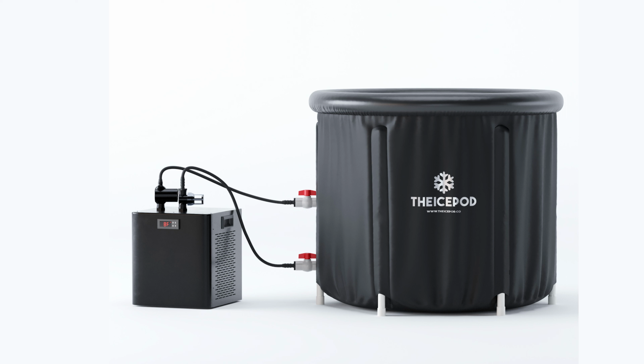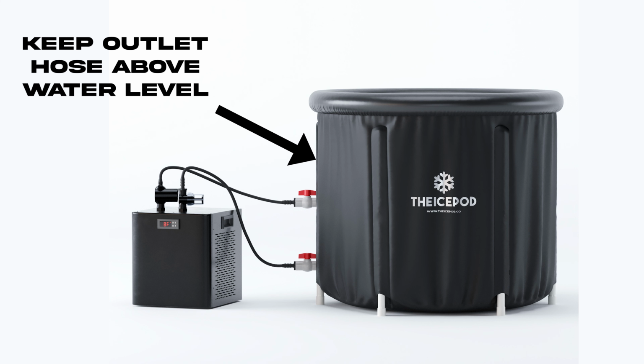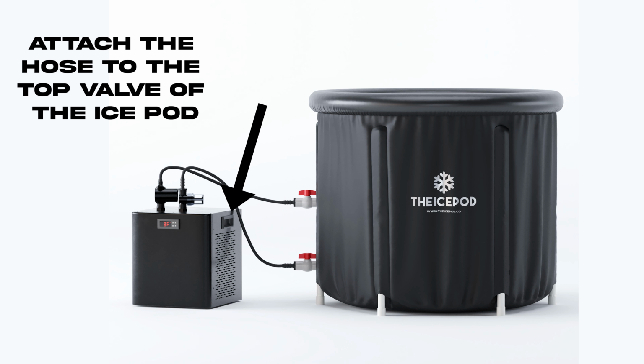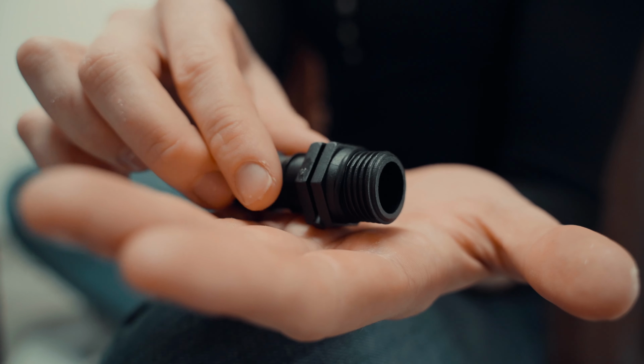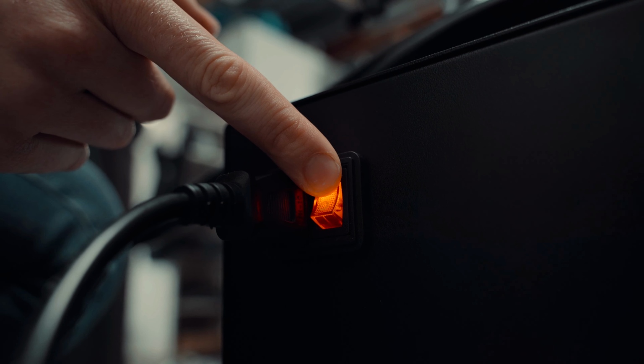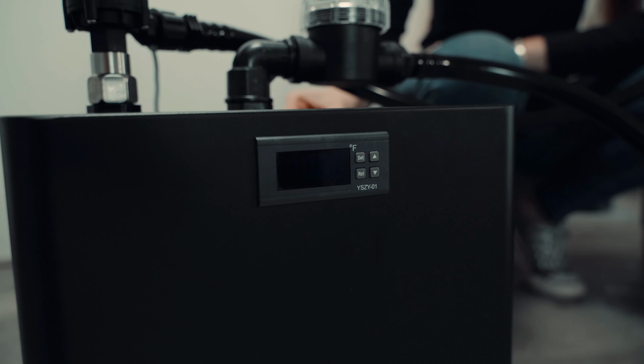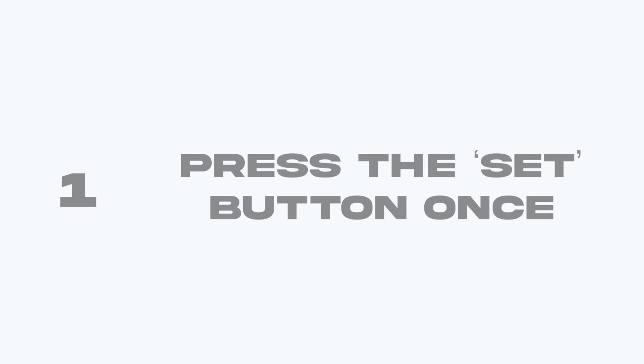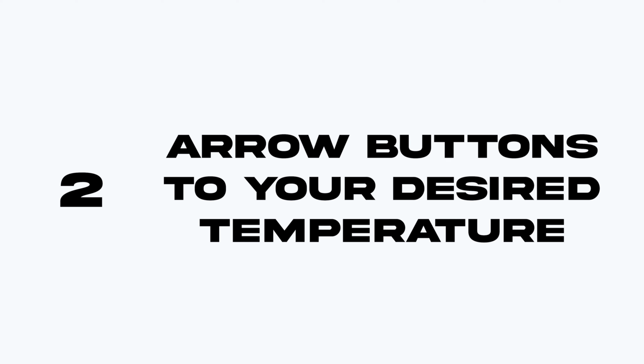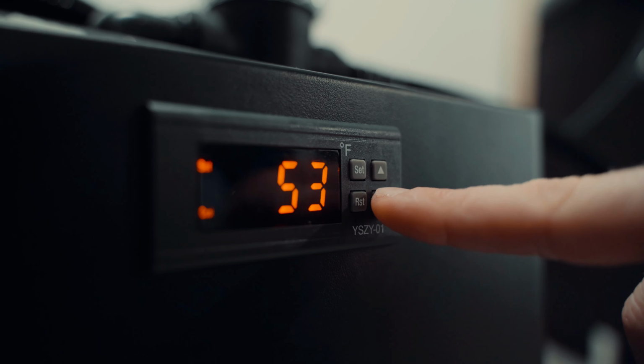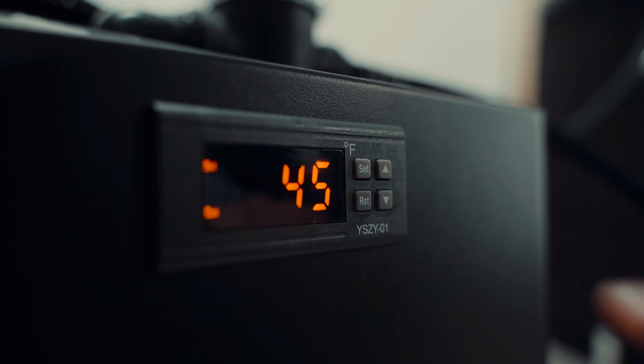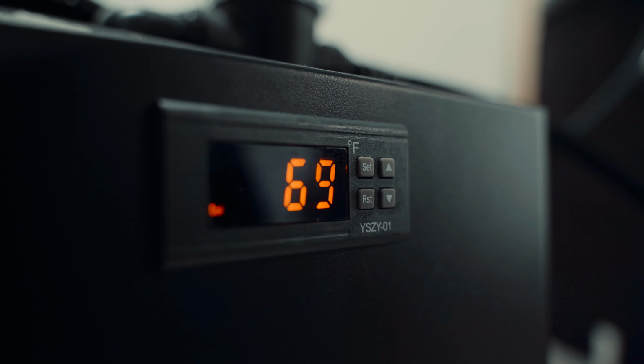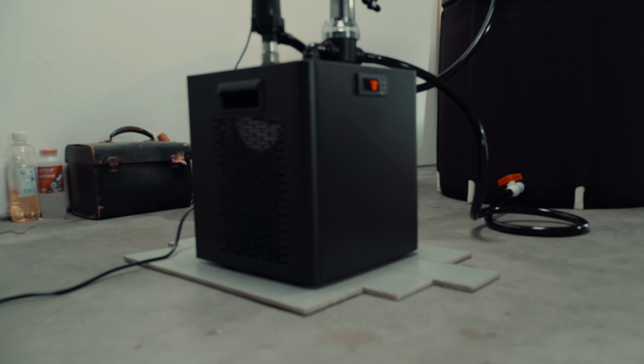If you have the 2-valved ice pod, please keep the outlet hose above water level so the water stays in. Then turn off the chiller and attach the hose to the top valve of the ice pod using the hose connector with a circular rubber seal. Turn the chiller back on once connected. Step 9. Controlling the chiller. Once your water's circulating, you can set your desired temperature. 1. Press the set button once. 2. Adjust the temperature up or down using the arrow buttons to your desired temperature. 3. Press the RST button once. The chiller will now show the current water temperature and will begin cooling down to the set temperature.